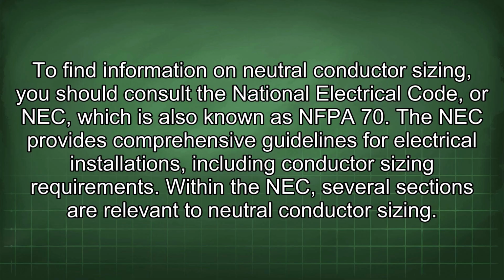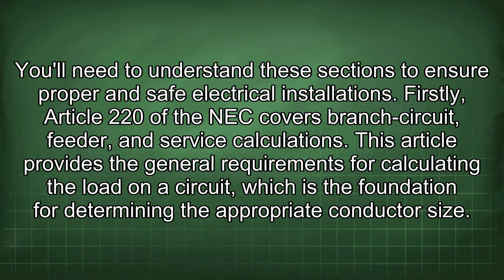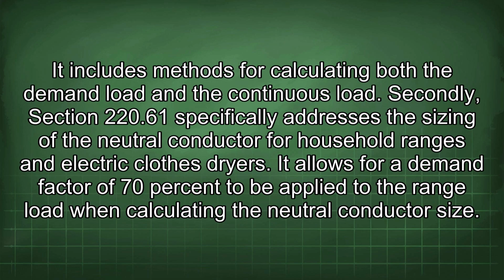Within the NEC, several sections are relevant to neutral conductor sizing. You'll need to understand these sections to ensure proper and safe electrical installations. Firstly, Article 220 of the NEC covers branch circuit, feeder, and service calculations. This article provides the general requirements for calculating the load on a circuit, which is the foundation for determining the appropriate conductor size. It includes methods for calculating both the demand load and the continuous load.